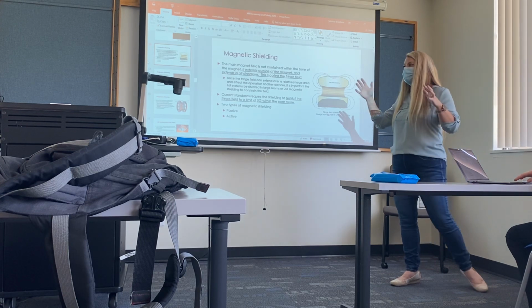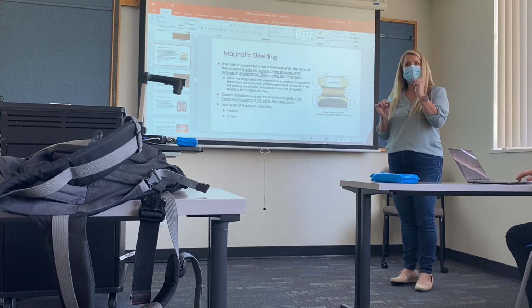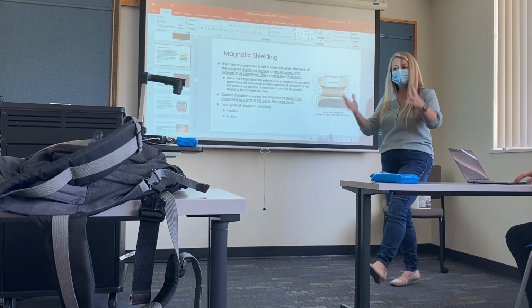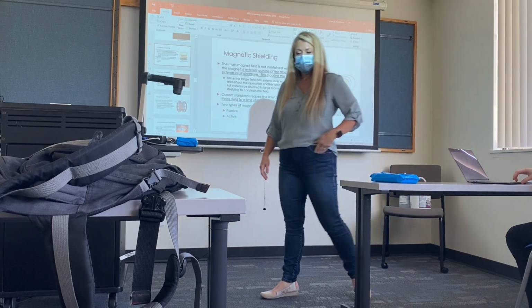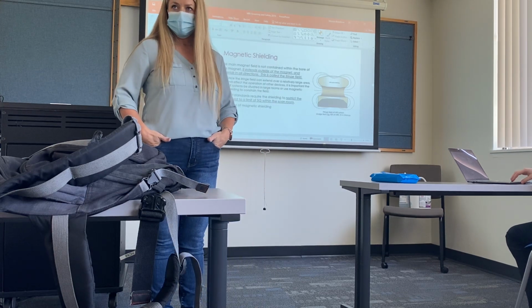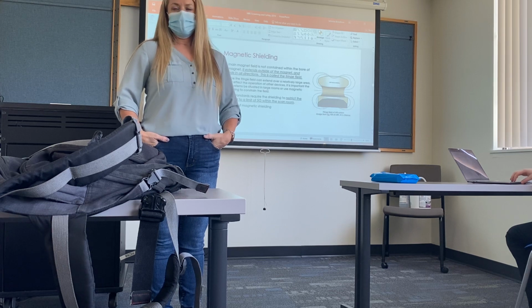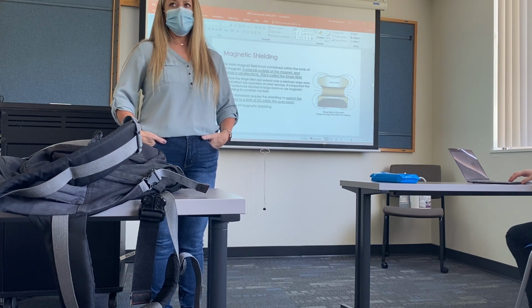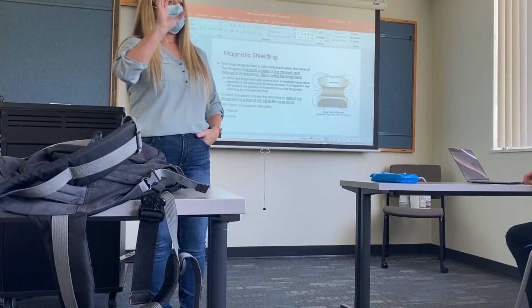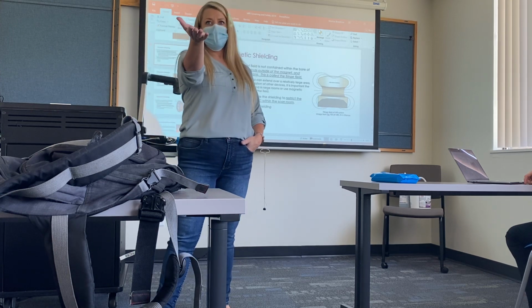Okay, so why is the magnet always on? What kind of magnet is it? Superconducting. It is a superconducting magnet. So what is superconductivity? It's the ability of a coil to sit in cryogen and maintain electrons without having to be plugged in. Yes, so what is the zero? Electrical resistance. Yeah, there's no electrical resistance. With superconductivity, why is there no resistance? The cryo. Super cold.